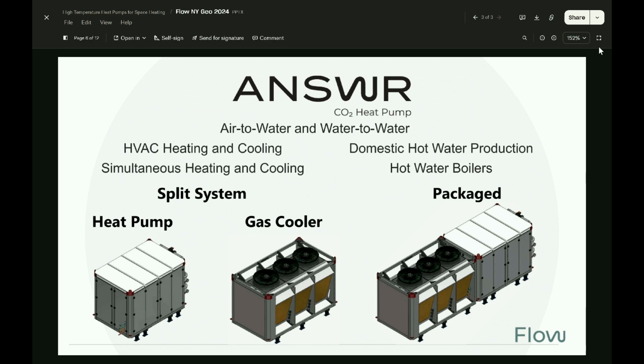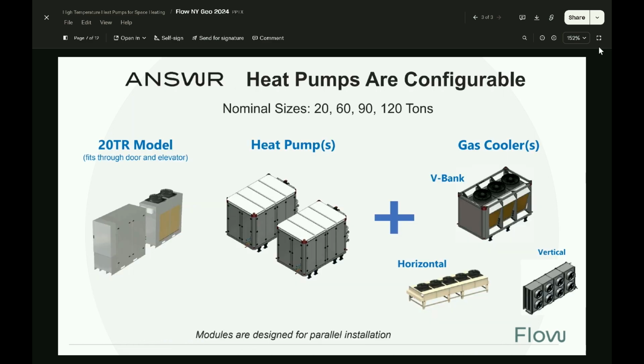If you wanted to do something more, we have our heat pump module — there's your water-to-water, you hook up power and water and you're done. Or there's the gas cooler side, which you can hook up as backup or primary, whichever way you need. You can split it by a huge distance, about five times more than traditional DX, or package it together to make it all one shot.